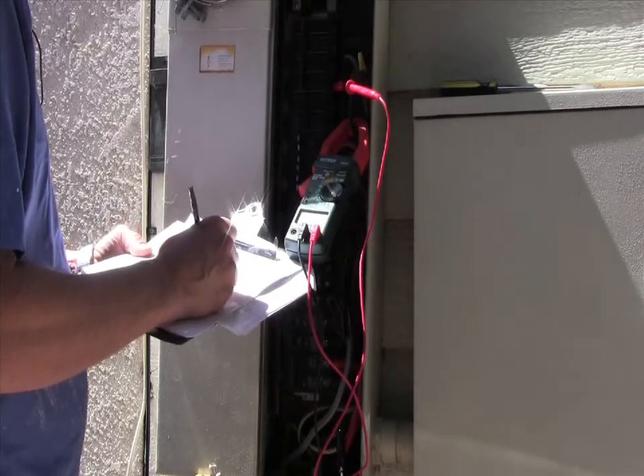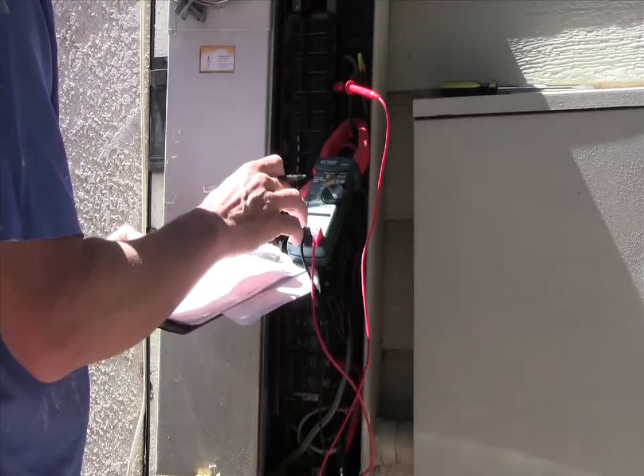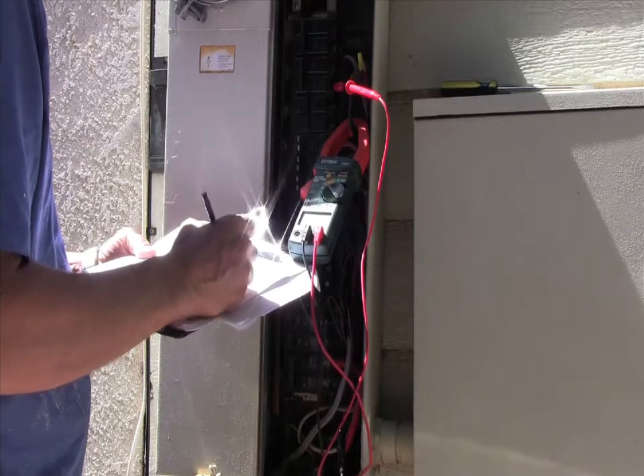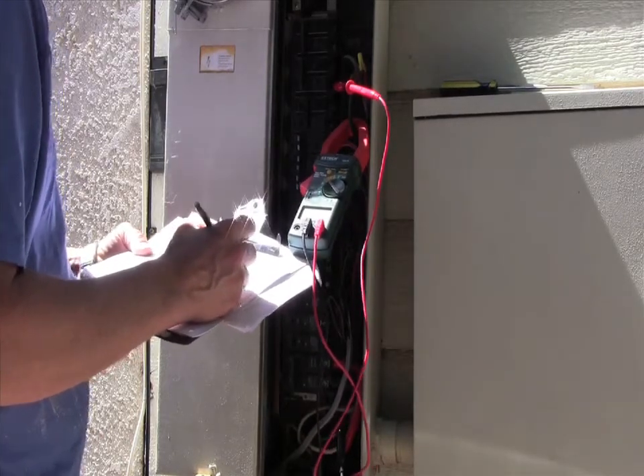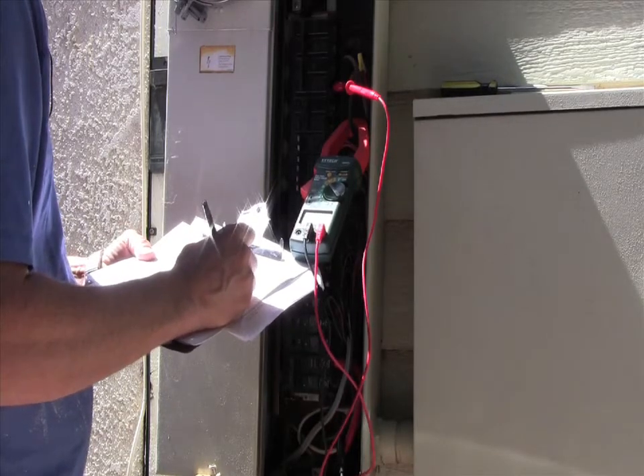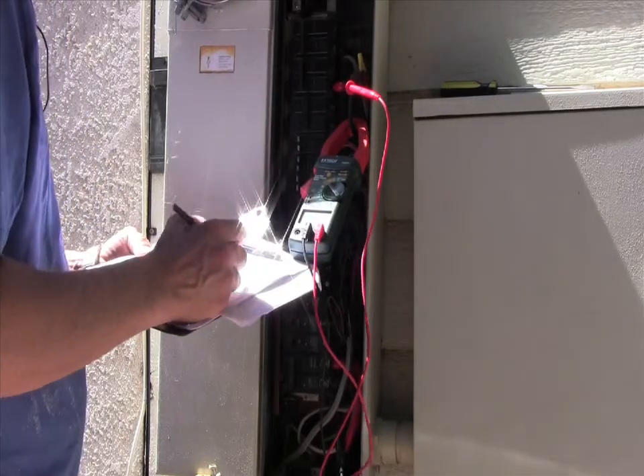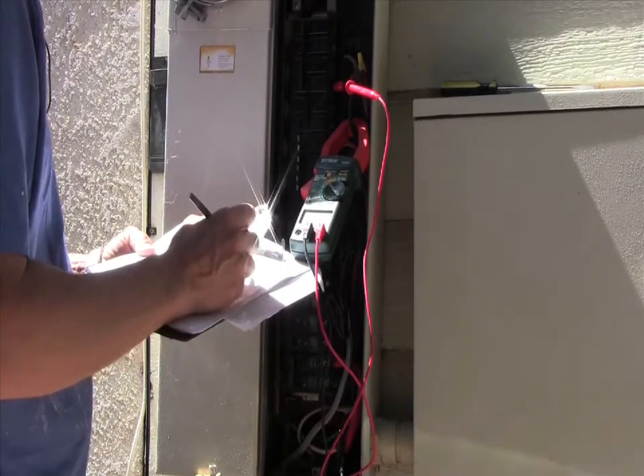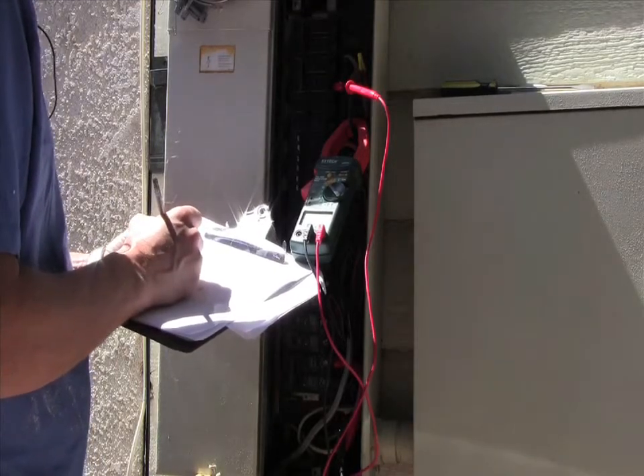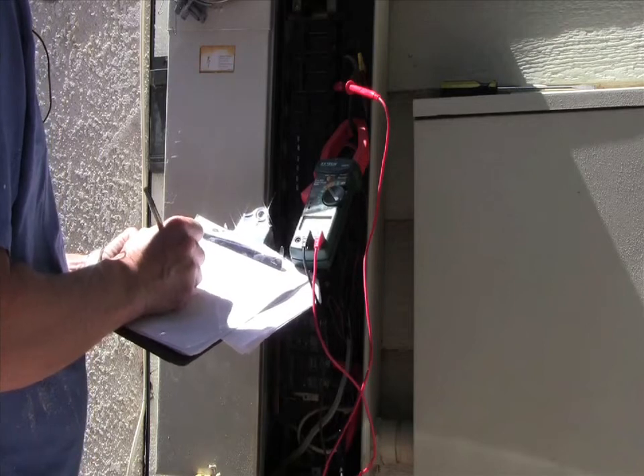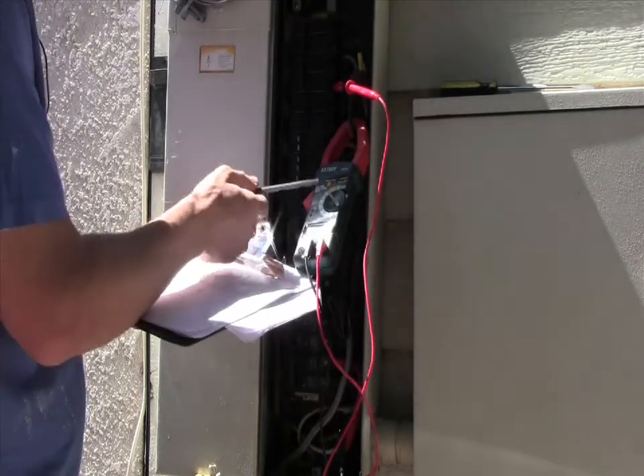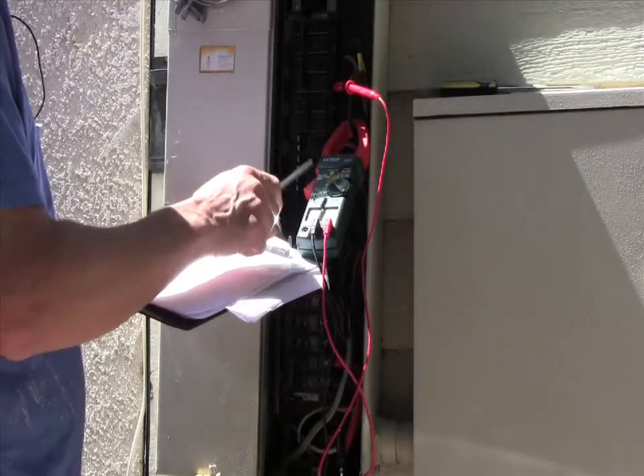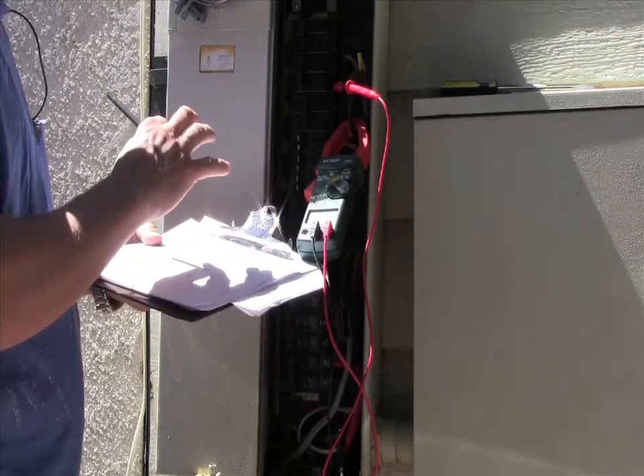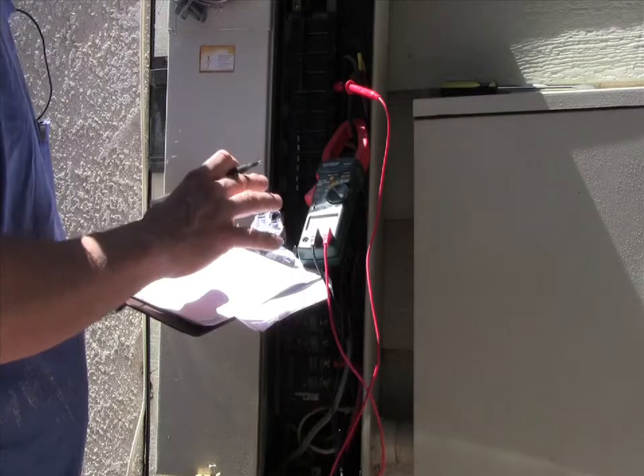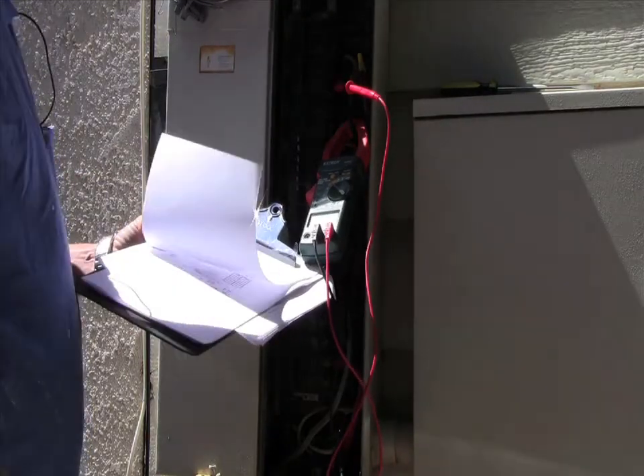It's at 1.22 kVAR. And it's lagging 32.3 degrees. And 2.27 kVA. It's at 121 volts and 18.75 amps. Now, for you guys that don't have a fancy meter like this, all we need is your volts and amps to do your actual install test or to do your sizing test, because we have a good ballpark idea of what it's going to take to correct the power factor and help save the customer some money.